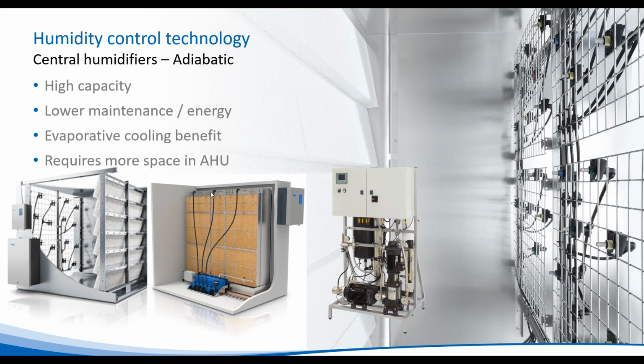Typically, this is what you'll see in a heritage application, in a main air handling unit. This is an evaporative humidifier, and it's got a tank of water at the bottom of the system. When we get a demand signal, water is passed through this hydraulic module, through these lines, to an encapsulated spray bar at the top of the unit. Water then cascades over this porous material, and as air travels over the porous material, it evaporates the water and cools the air as it goes. And that's fantastic. All you're running is a small pump of about 0.25 kilowatts, so very efficient. But you do need to preheat the air. And that will typically give you plus or minus 10% RH control.